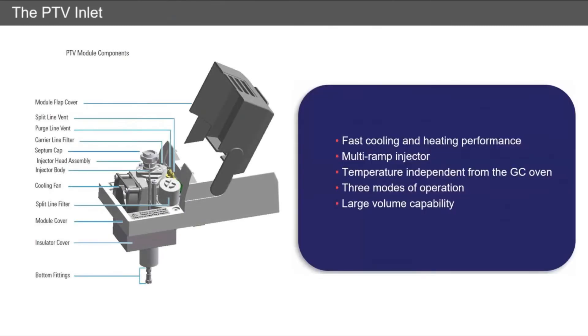We're moving on to the PTV inlet now. The PTV inlet has fast cooling and heating performance. It's designed to run at multiple ramps and the temperature control, like split/splitless, is completely independent from the GC oven. It's got three modes of operation which we'll look into and it has large volume capability.